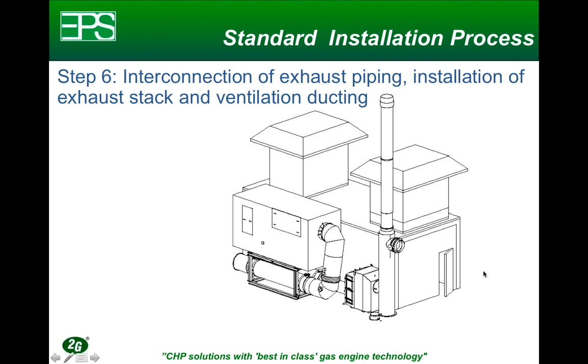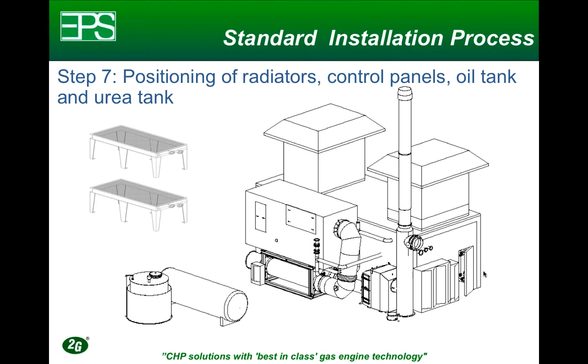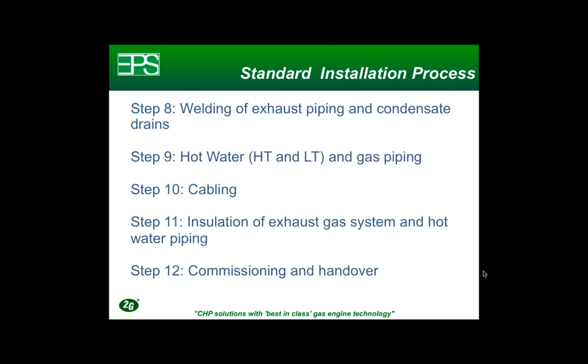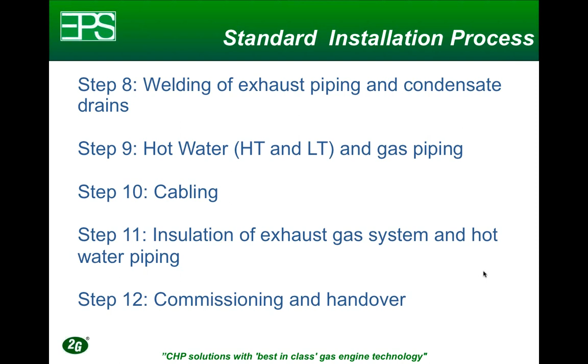Then the enclosure is closed up, and some of the main piping, interconnecting exhaust piping, is installed, and then the ventilation ducts and silencers are mounted on top of the enclosure. Then the oil tank, urea tank, radiators, and control panels are positioned. Once that's all in place, the interconnecting piping is installed, the welding of the exhaust piping is done, cabling and control wires are installed, and once that's all complete, the system is ready for commissioning and handover.